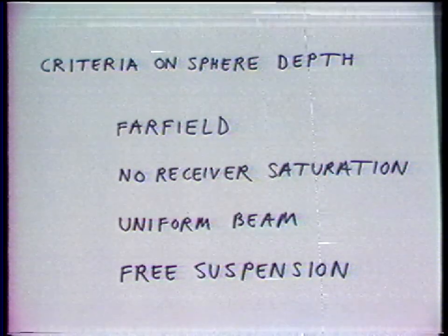The exact sphere depth is determined by several criteria. These are that the sphere be at a sufficient far-field range that the receiver not be saturated by the echo, and that the beam be uniform over small lateral ranges. The range must also be chosen to ensure a free suspension.